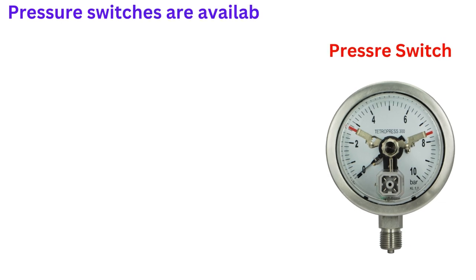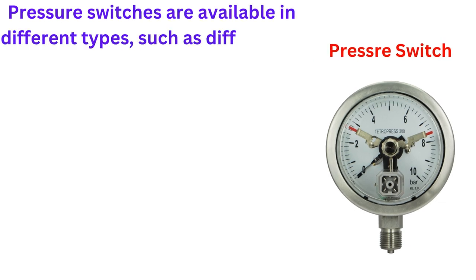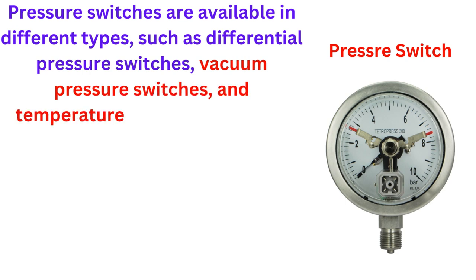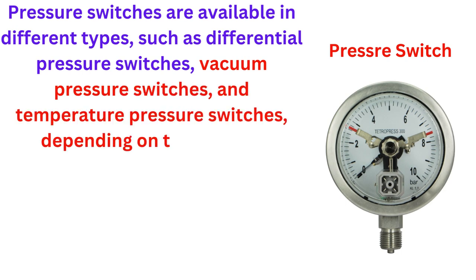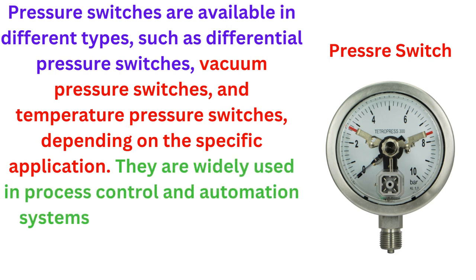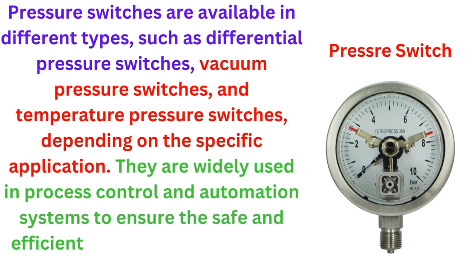The pressure switch consists of a sensing element, typically a diaphragm or a piston, that responds to changes in pressure. The sensing element is connected to a mechanical switch, which opens or closes an electrical circuit when the pressure threshold is reached.